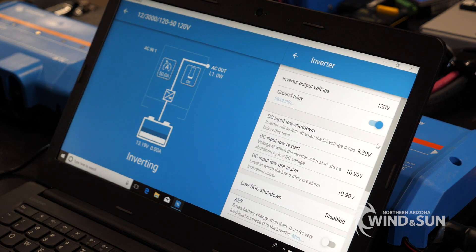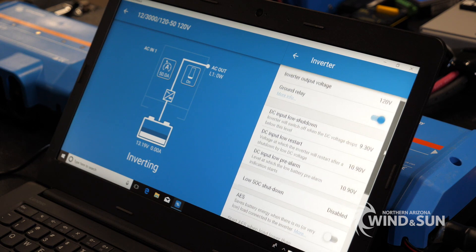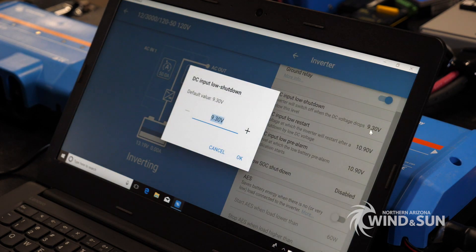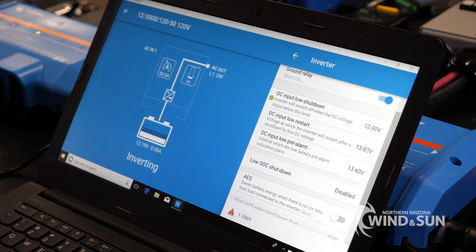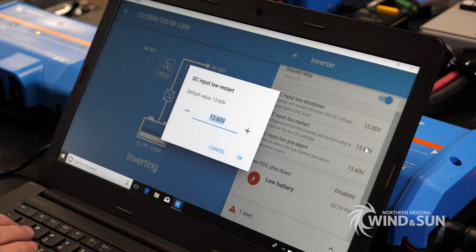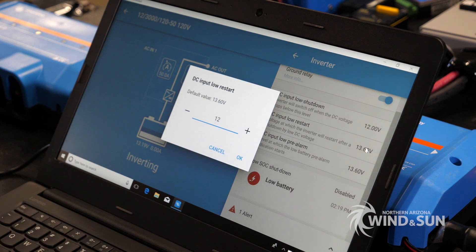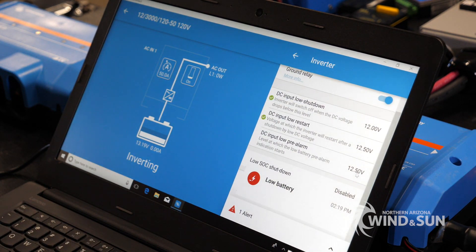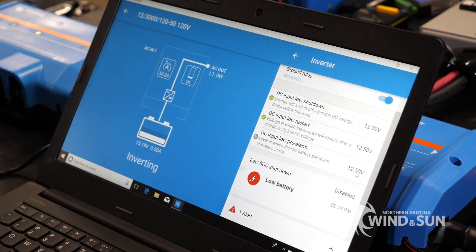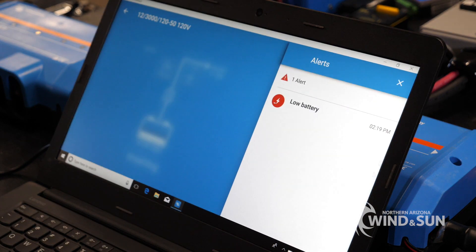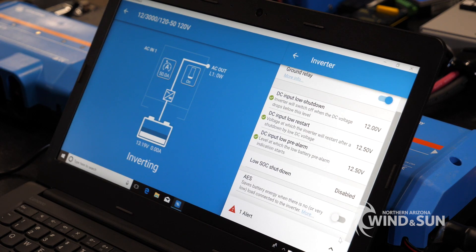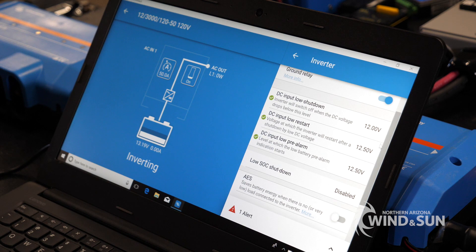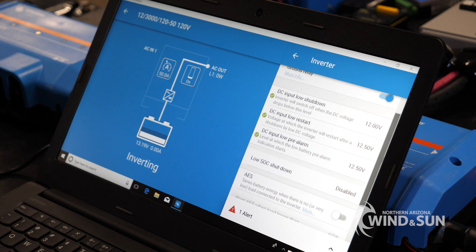Under the inverter tab, we're going to come in here. We're going to adjust the low battery cutout. For this particular project, I'll just set it to 12 volts. And we'll set this to 12 and a half volts. The pre-alarm at 12 and a half will be fine as well. That will likely pop up if your battery voltage is below the pre-alarm. So we triggered a pre-alarm because, by default, it wanted the value up much higher.